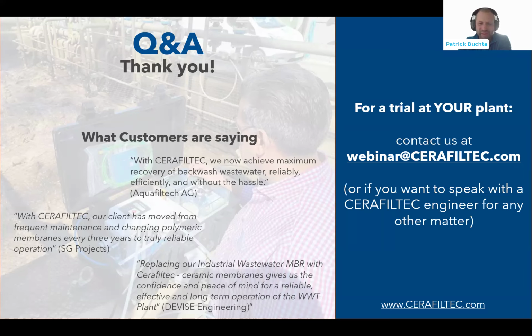First of all, the membranes are not brittle at all. I forgot to mention when I introduced the technology that aluminum oxide has far higher flexibility than silicon carbide, for example. That's why we make use of this material. And typically it is not breaking. That is the big advantage. The risky moment is the installation. You sometimes experience that somebody throws a screwdriver from the top of a tank or a drilling machine, and the person installing does not catch it. That can be a problem if the membranes are not protected during installation and our recommendations are not followed. But typically, this is not the case.